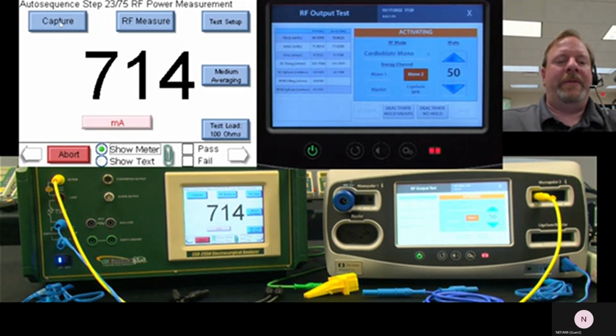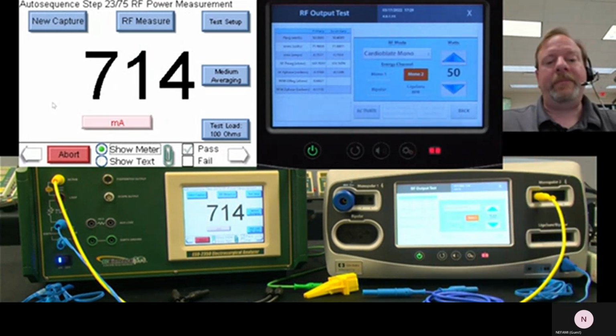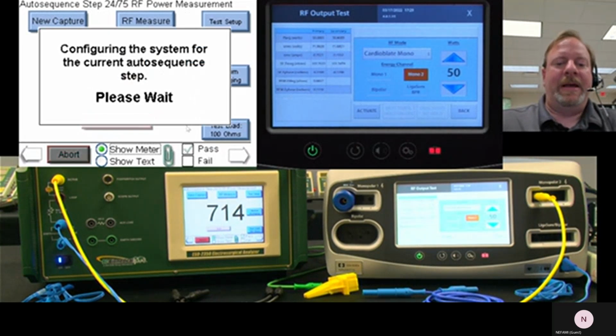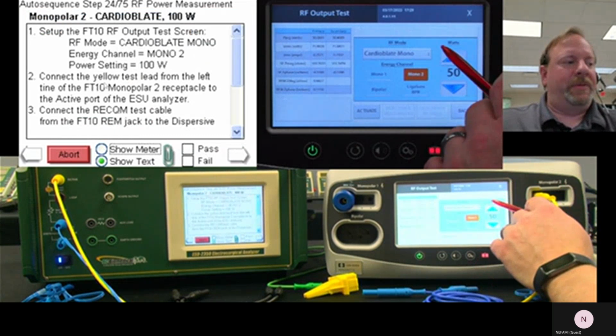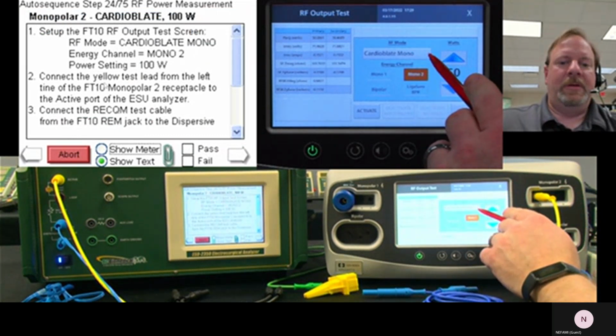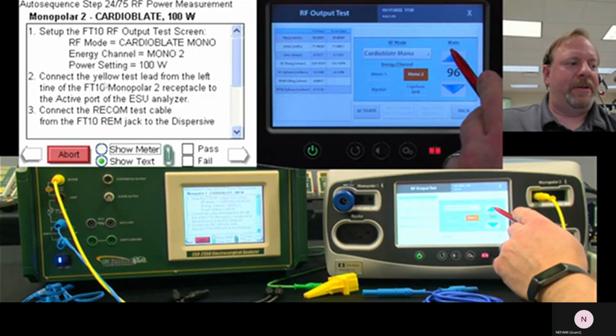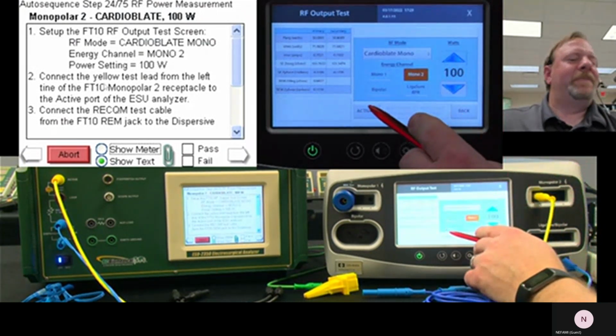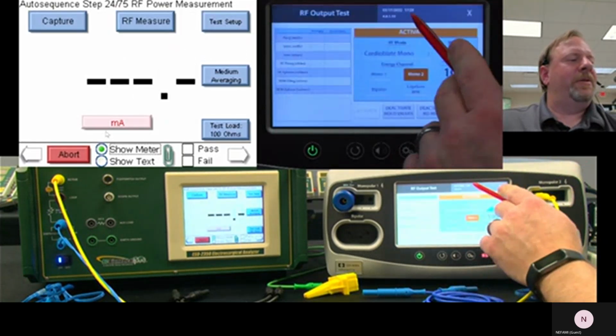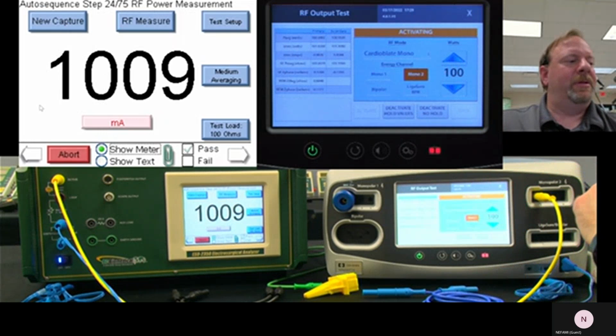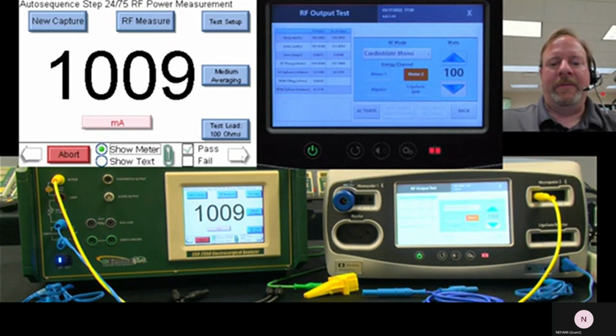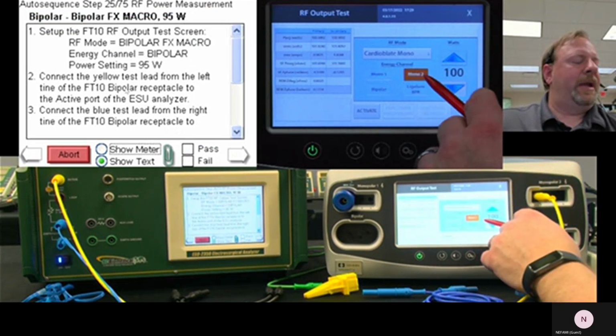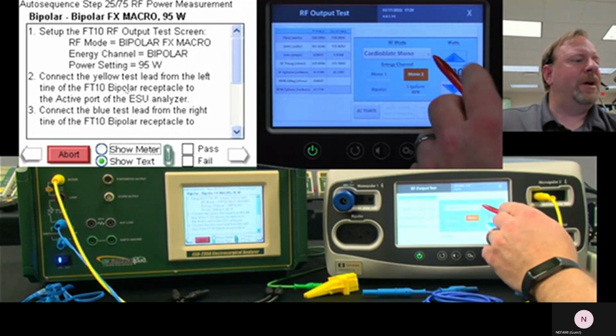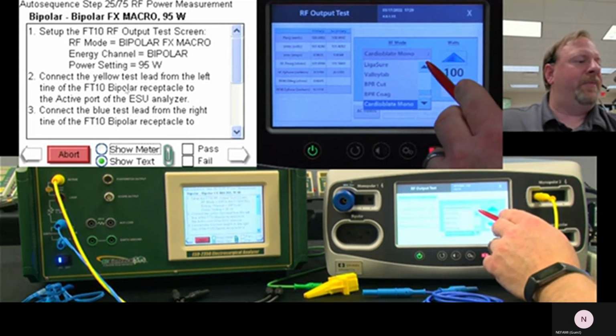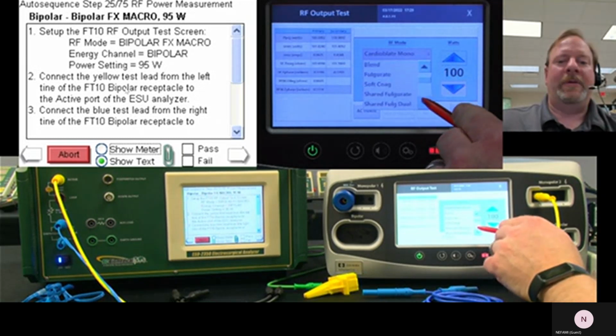Now, the reason we have to do all this manual setting: if you've ever done the Force Triad auto sequence on the 2400, you'll notice that it's completely automated. You plug in an RS-232 cable. Now, I'm dangerous here. I'm talking and trying to do this at the same time. This is when I make mistakes. So the ESU 2400 and the Force Triad have a communication cable, and we worked with Covidien to develop that auto sequence and the communications to the Force Triad. And so when they developed the FT10, we said, hey, it'd really be a good idea if we do those auto sequences again. Can we talk to the, oh, now we're doing bipolar.